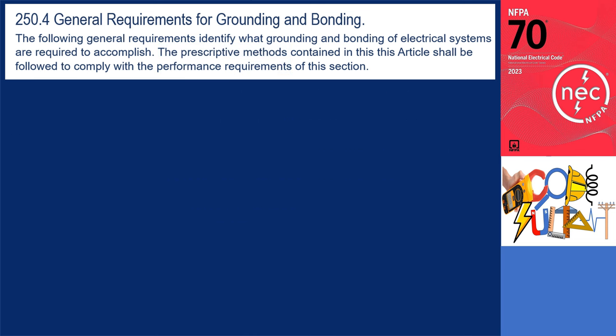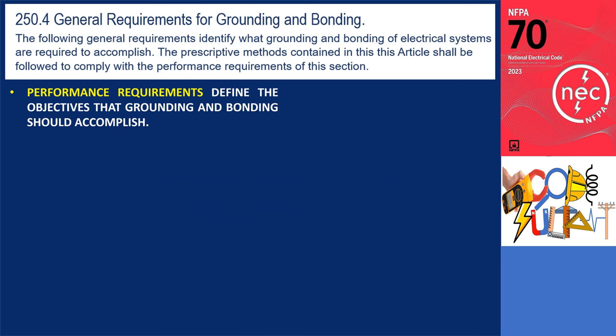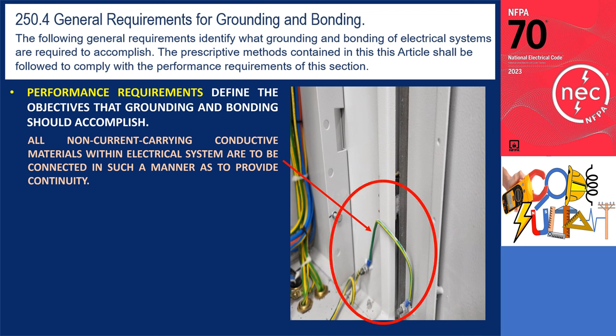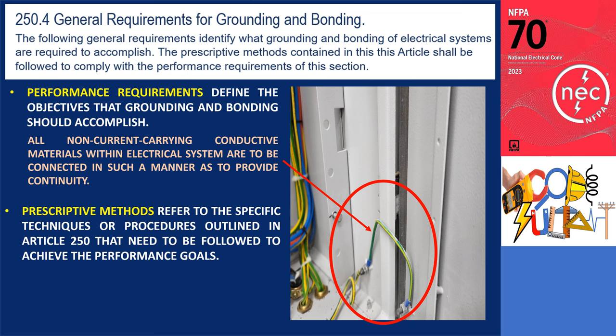Let's further clarify the concept of performance requirements. Performance requirements establish the desired objectives that grounding and bonding practices should achieve — they serve as the benchmark for expected outcomes. For instance, one performance requirement states that all non-current carrying conductive materials within the electrical system must be connected in a manner that ensures continuity. Prescriptive methods refer to the specific techniques or procedures outlined in Article 250 that must be followed to fulfill these performance goals.